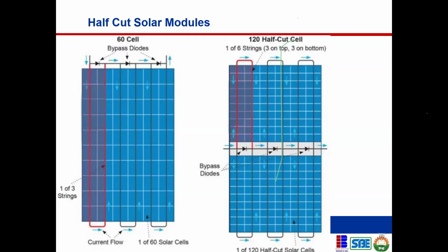Now, if you have multiple solar modules in one string, and this kind of thing happens, all the solar modules in that string will be reduced. But because of the diode, once this happens, it's only going to affect this one. Every other solar panel, every other module will work optimally. And that's the importance of having diodes in your solar modules.